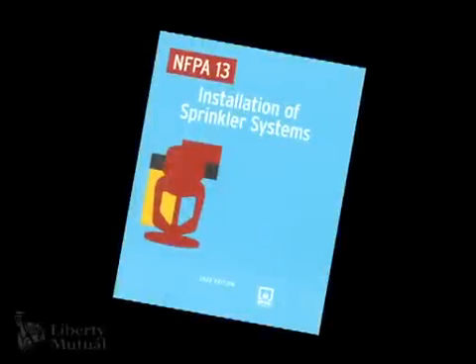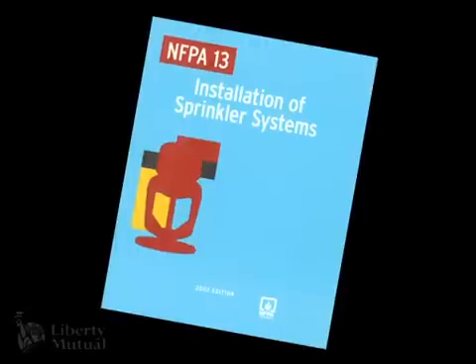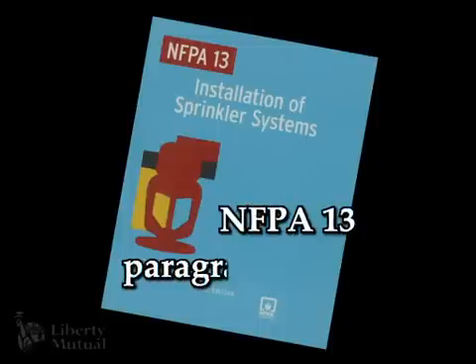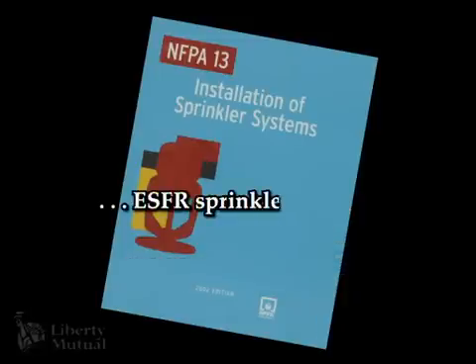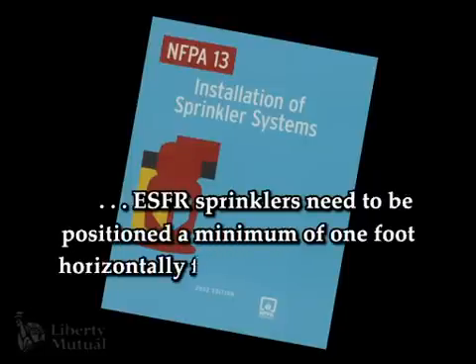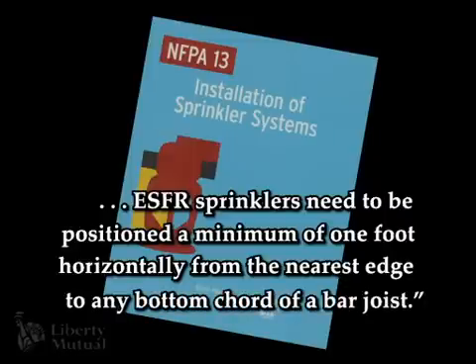Any obstruction below pendant early suppression fast response, or ESFR, sprinklers may interfere with the proper performance of the sprinkler. NFPA 13 paragraph 8.12.5.3.3 states that ESFR sprinklers need to be positioned a minimum of one foot horizontally from the nearest edge to any bottom chord of a bar joist.